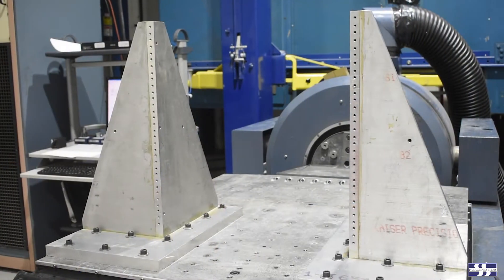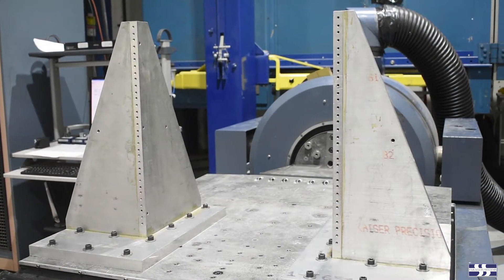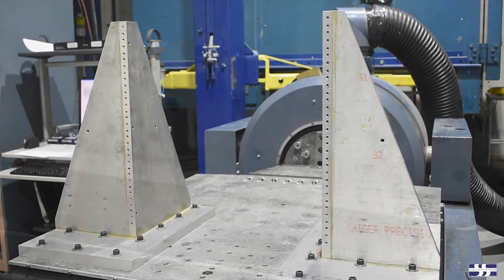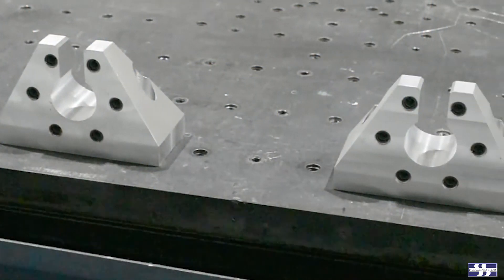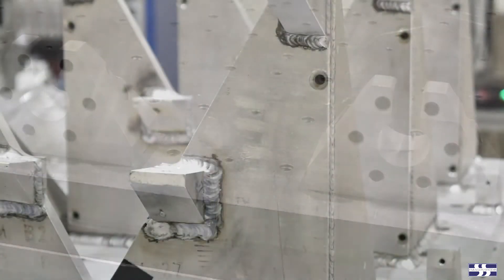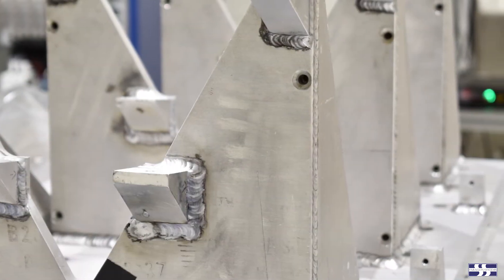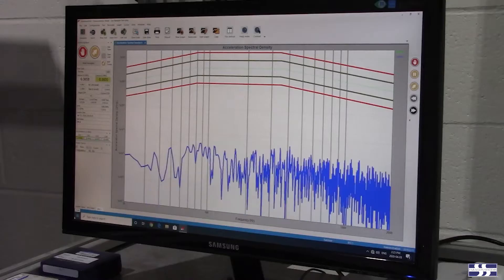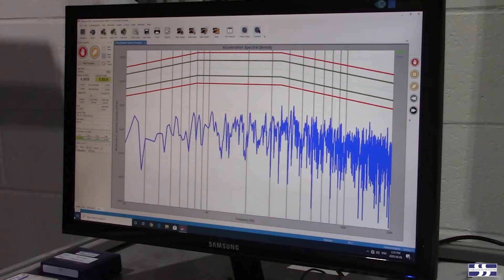Frequently though, even with a good fixture design, it isn't always possible for a vibration fixture to be completely free of resonances or attenuation regions in the frequency range of the test profile.